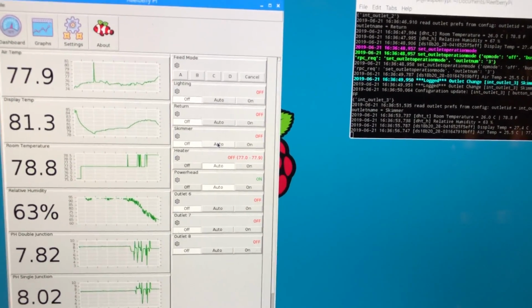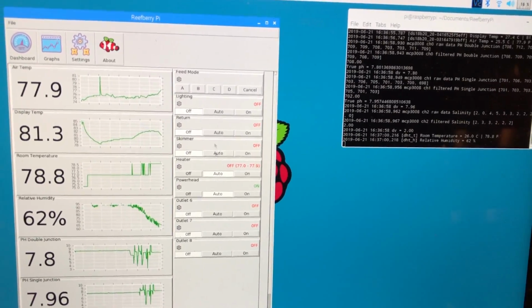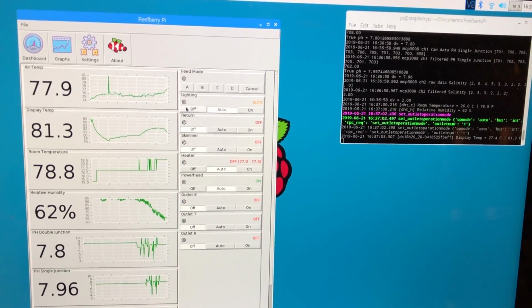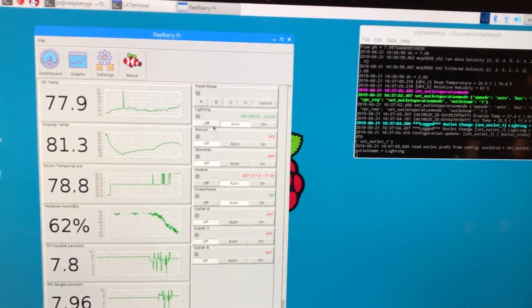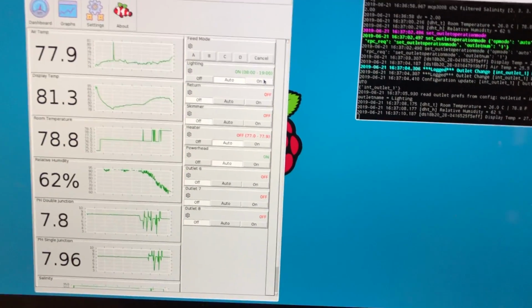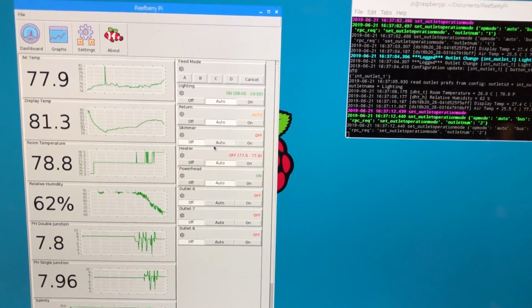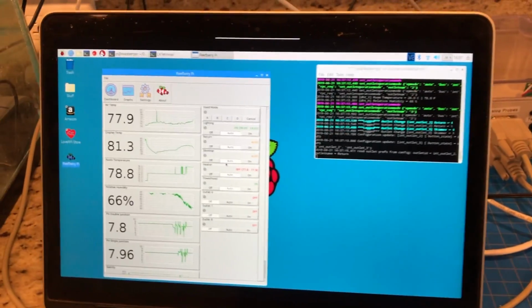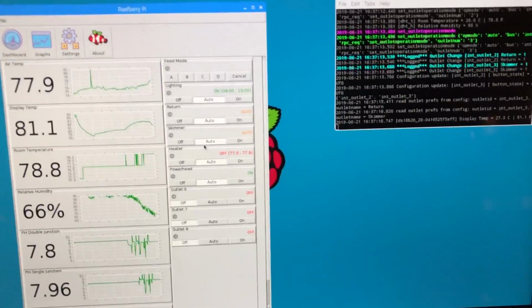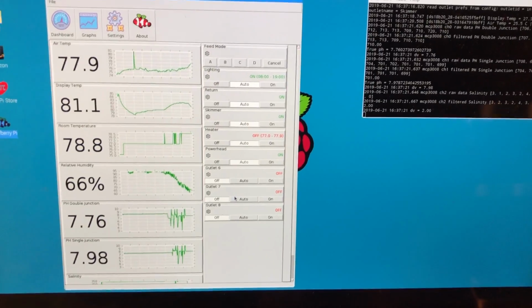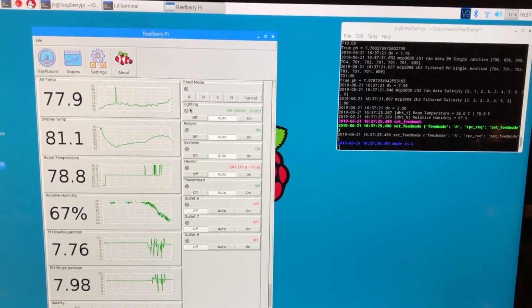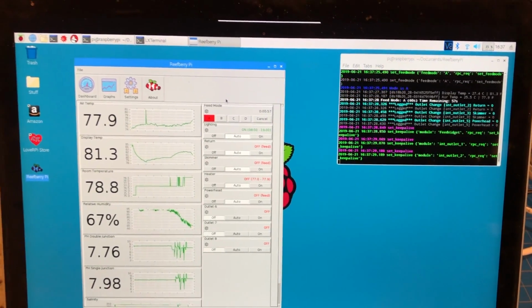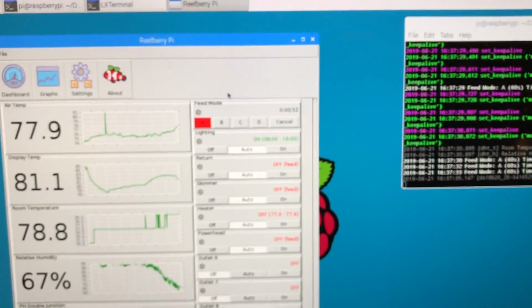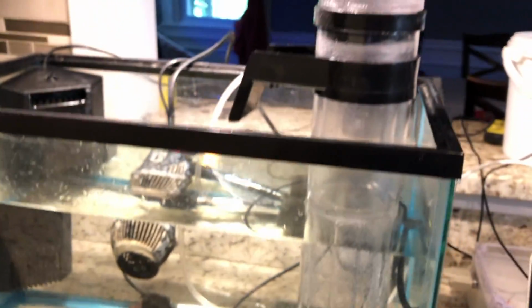If I hit auto, it's going to run the program that we put into there, which means it's going to basically run whatever we had set in here. So you have the option to turn it completely off, just keep it on, or run the program. So we're going to hit auto. We're going to run all the programs, which means now if we hit A, feed mode A, these should react according to the programming that we put into there. So we're going to do that now and hit A. And we're now in feed mode A. And we had that configured for 1 minute, so it's starting a 1 minute countdown. Which means all the stuff will just sit off for the time being.